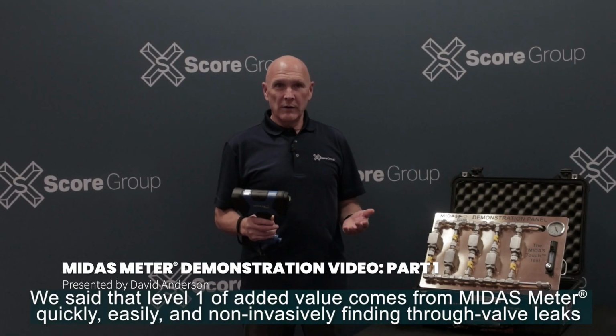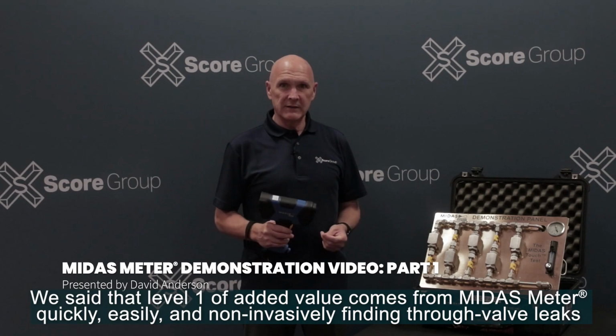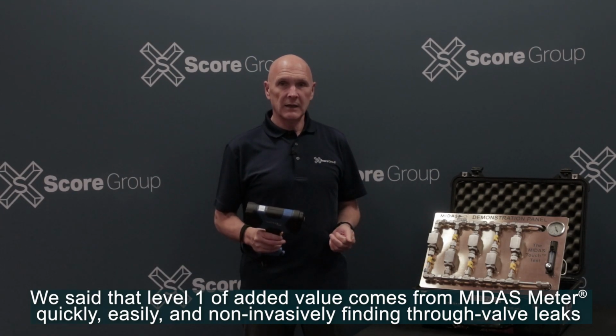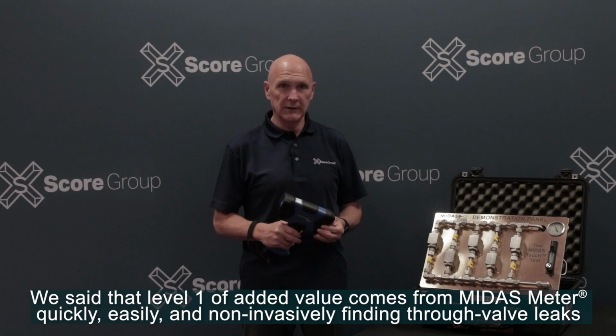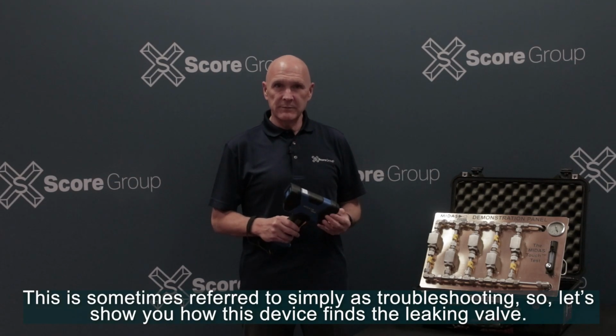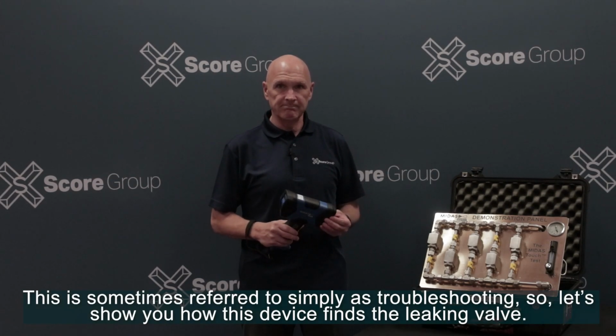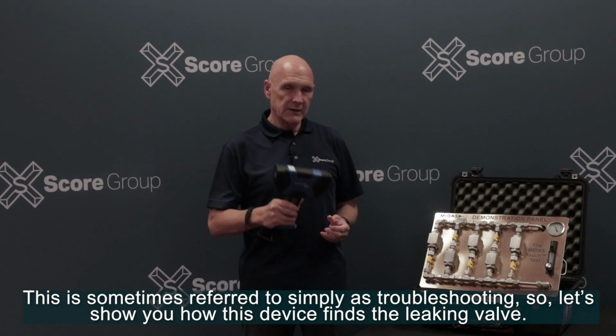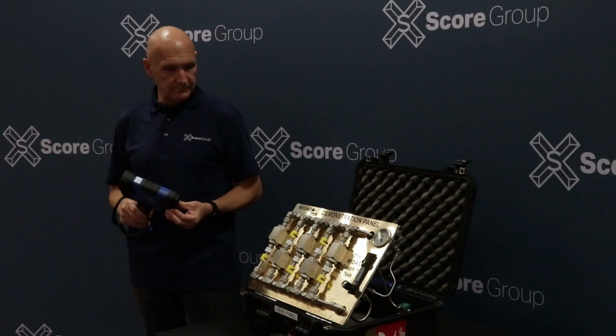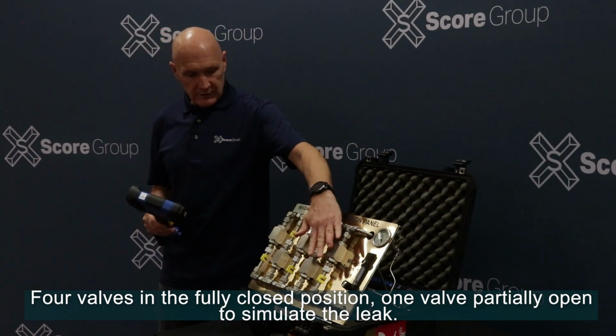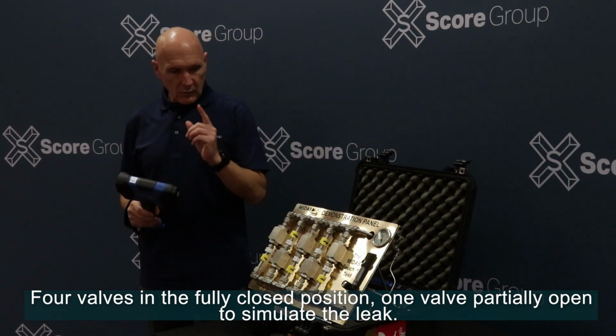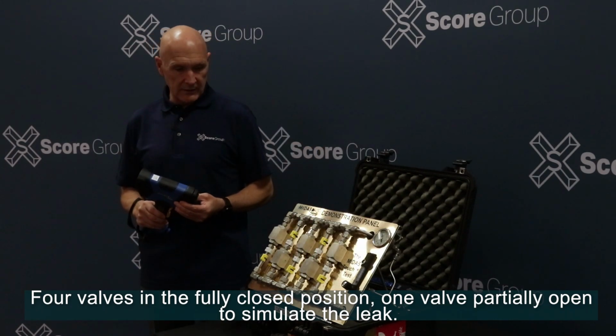We said that level 1 of added value comes from MIDAS meter quickly, easily and non-invasively finding through valve leaks. This is sometimes referred to simply as troubleshooting. So let's show you how this device finds the leaking valve. 4 valves in the fully closed position, 1 valve partially open to simulate the leak.